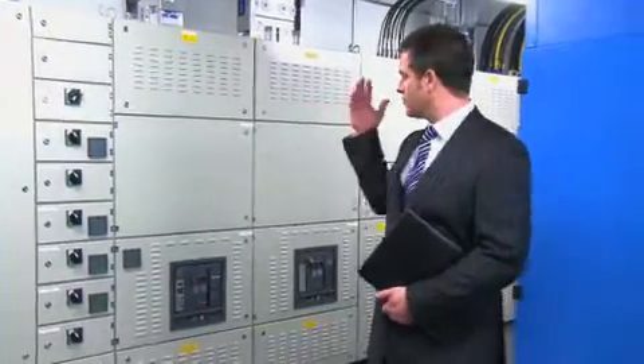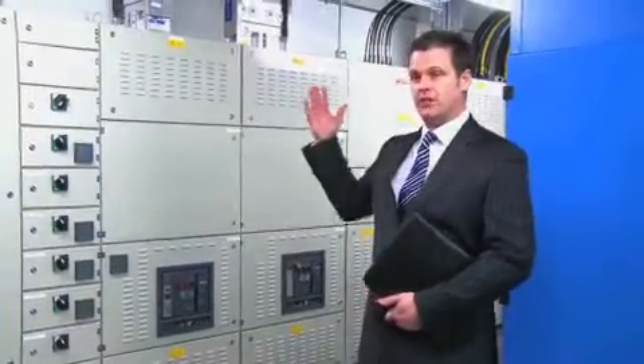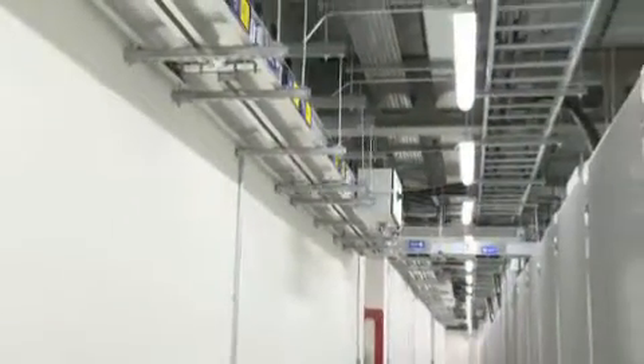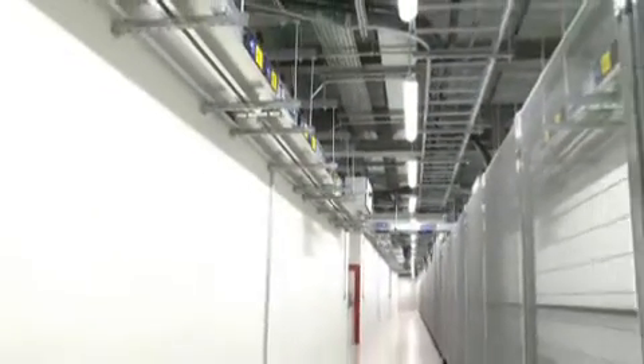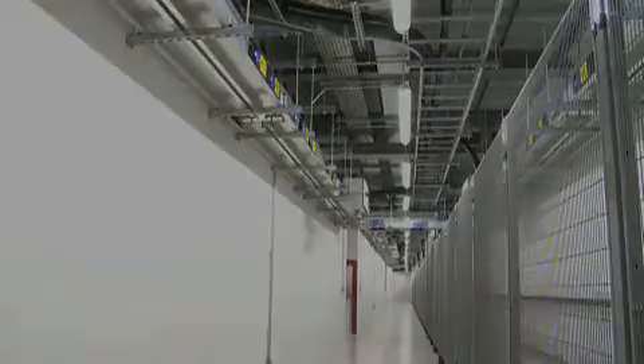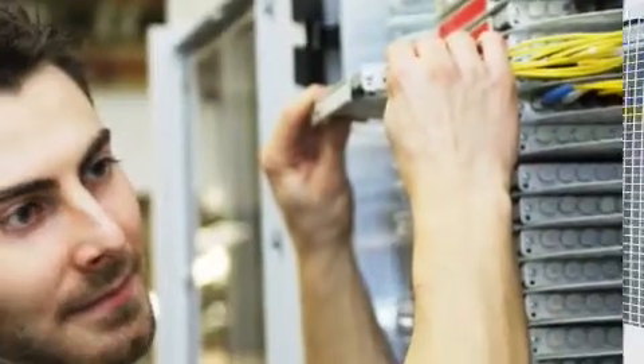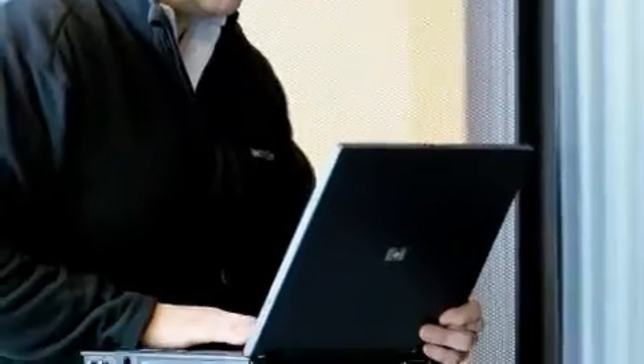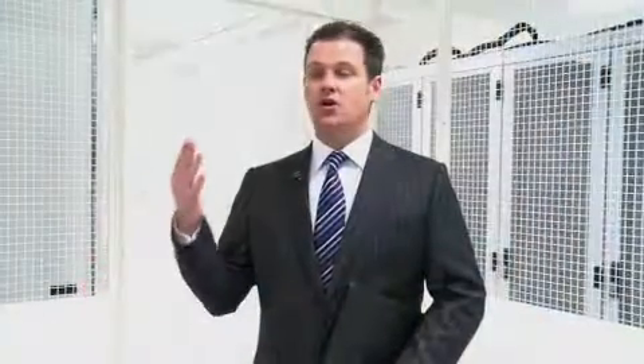The power then goes to an output panel. The output panel then feeds the busbar system, and the busbar system takes the conditioned power to the PDUs within the data suites. This is where we provide the resilient power and the resilient cooling for our clients. We have the flexibility where we can offer 2 kilowatts, 4 kilowatts or 20 kilowatts a rack, either in N+1 or 2 N+1.